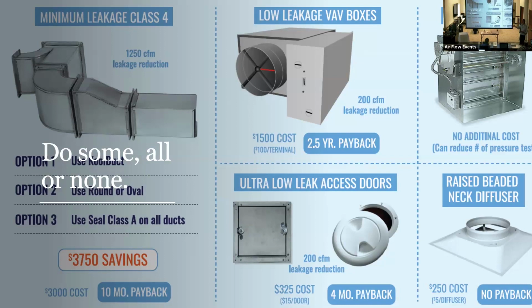Not that big of a deal, but if a contractor's buying diffusers and your diffuser costs $5 more, you're losing that job. It's not happening. Life safety damper, low leak sleeve, no cost. And then if you buy this higher end ductwork, it's gonna cost, but it'll have a payback. Now, who measures this? Nobody.